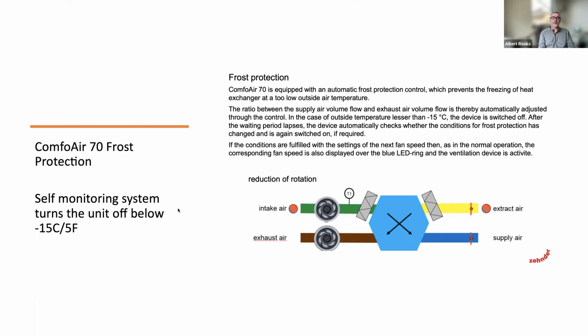So this device will look at all the temperatures, and the first stage, when you get a few degrees below freezing and you can start frosting up the core, it'll slow down the intake fan and keep the exhaust fan flowing. So that'll throw the unit out of balance, but you still have a stream of exhaust air going out that's not reintroduced into the supply air. And you've slowed the supply air, the fresh air coming in, and the exhaust air is going out a little faster. So that generally warms the core and keeps it from icing up. And then finally, when that is no longer possible, it'll just turn the unit off. And it'll just be off for a while. There won't be any ventilation until the temperatures warm up, and away she goes. So in some climates, this is not the appropriate thing to do. And in some climates, it's a fine thing to do.